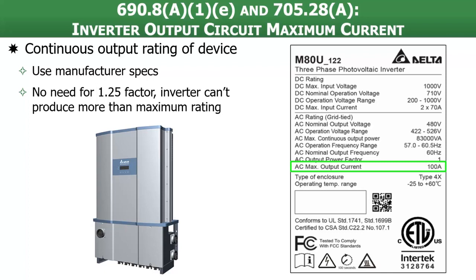So in the case of this particular inverter that we see on the slide, we can see the specs for that inverter on the right side here, and we see the AC maximum output current for this inverter is 100 amps. And so that is what we would use for the maximum circuit current value for the output circuit of this inverter. And we're going to use the manufacturer's spec sheets to determine that, or the labels on the inverter. Just, information has to come from the manufacturer.